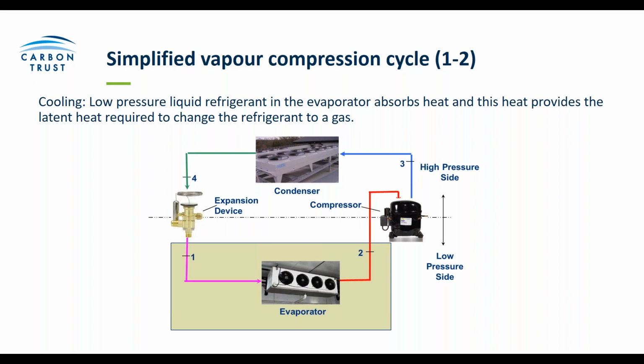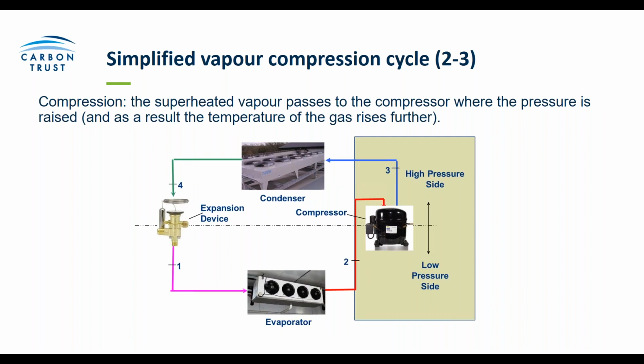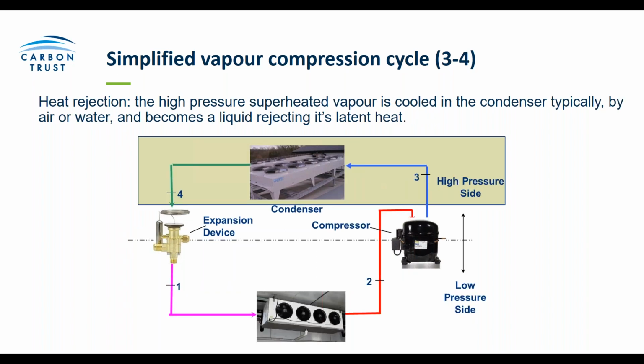So moving on to the next stage of the cycle, this is the compressor. So this is where the superheated vapour that was once a liquid is now transferred, and is probably the most energy intensive part of the process. So being able to reduce the work that's done here is going to pay dividends in terms of your energy savings. It's where you can make probably the biggest savings in your refrigeration system. So in this part of the process, the pressure is increased, and it's this pressure increase that moves the heat, the refrigerant, to the condenser. So this is essentially the part of the system that removes the heat, usually to an external source. It's where you can consider the heat as being essentially dumped.